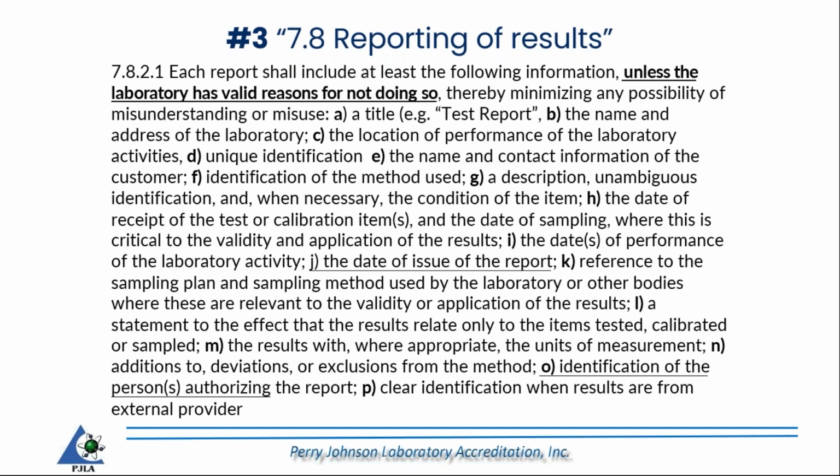And then the person authorizing the report. So under 6.2, under authorization, you have to authorize individuals to issue reports to the customer. So even if it happens for smaller organizations, if it's the same person that's wearing two hats in this scenario where they're actually doing the test or calibration, they are doing the report. Ideally, yes, they're reviewing that report before it's issued. Need to capture that separate date of issue, and they also have to be identified as the person authorizing the release of the report.